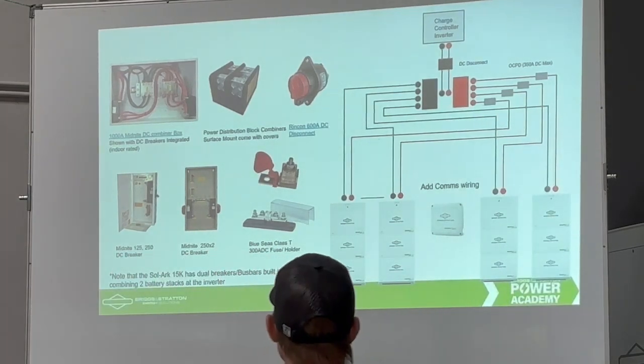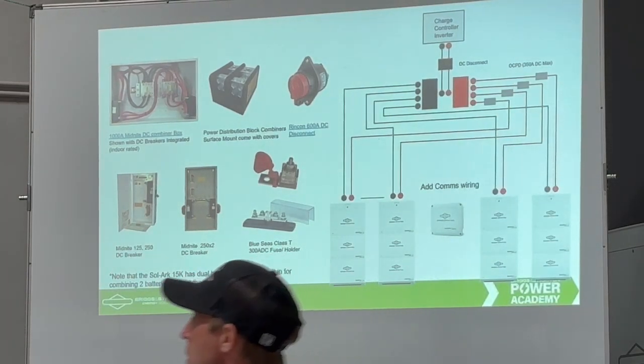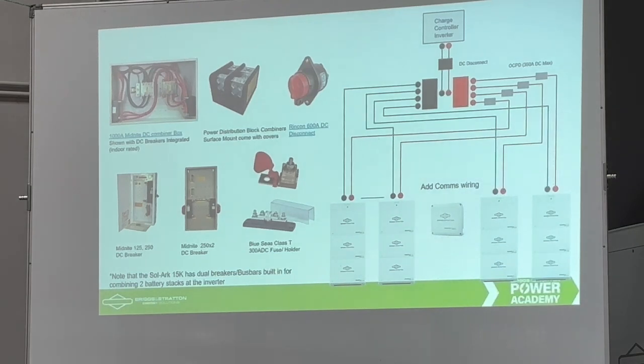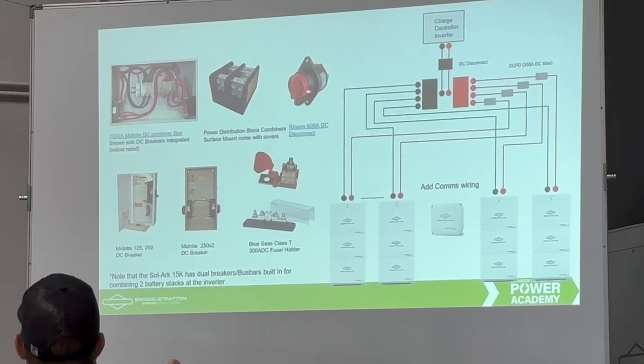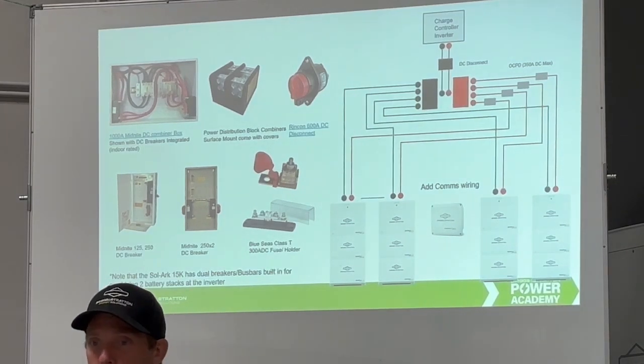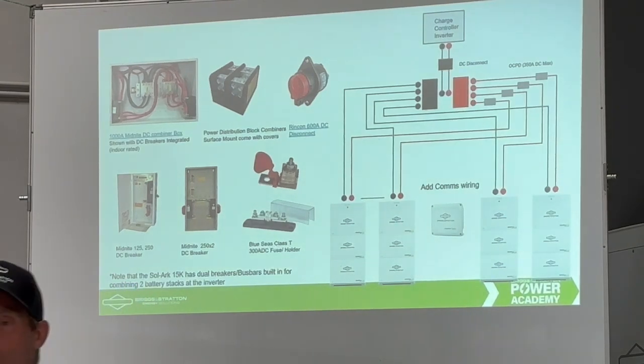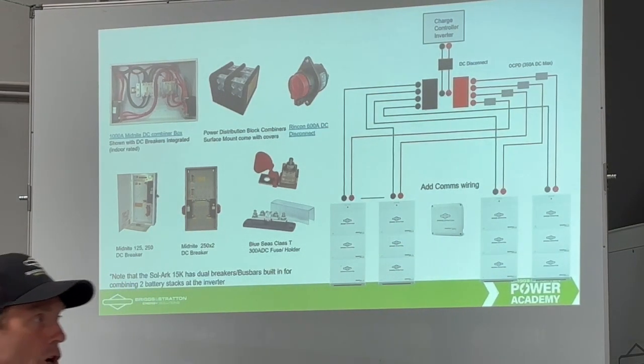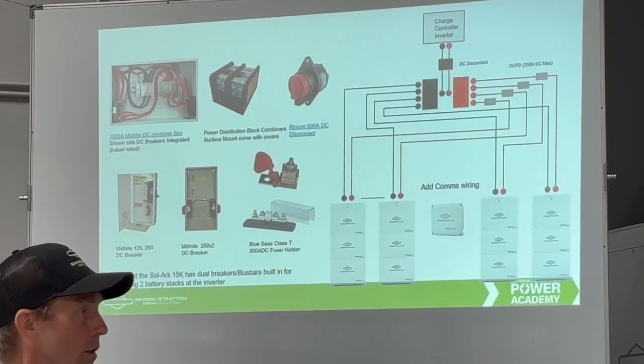That could go, it's not required—it depends on your AHJ—but if your AHJ requires a DC disconnect, you could wire it between the battery controller and the Sol-Ark. These are surface mount, so you could get an enclosure and mount it on the surface. John's unit, the gray one, has those disconnects.